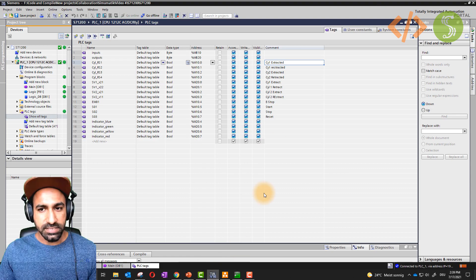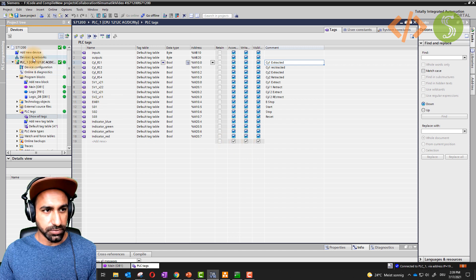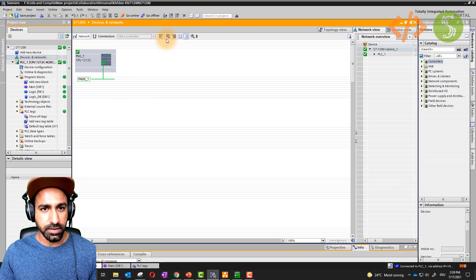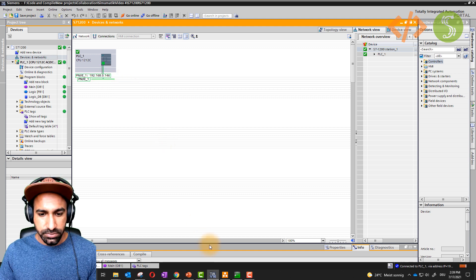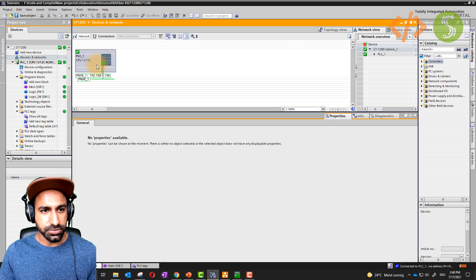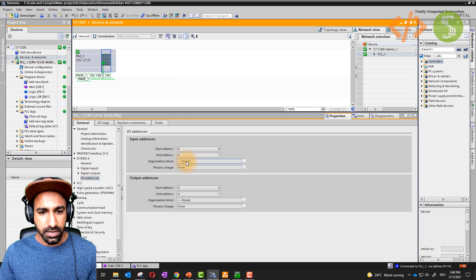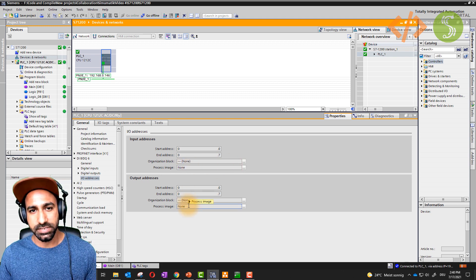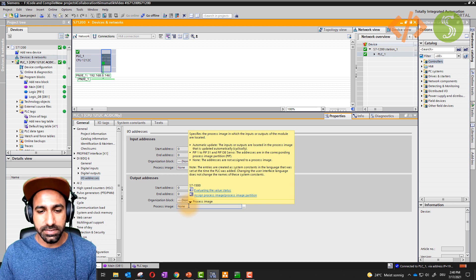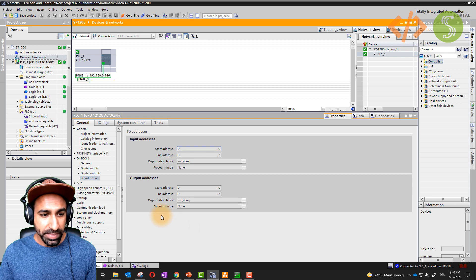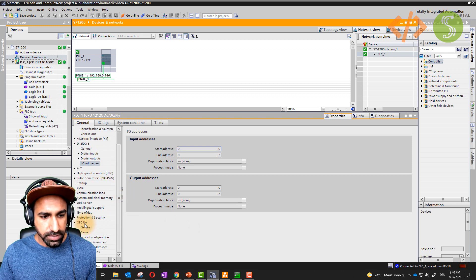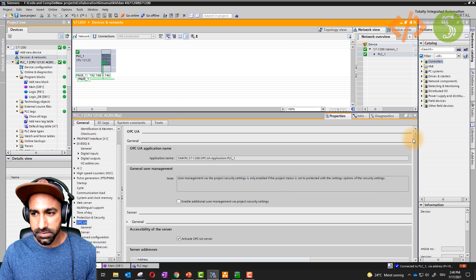Let's see step by step. First I'll open my TIA Portal, where I have defined my PLC. In Device and Network, my PLC is located here with IP address 192.168.0.146. Going to the properties of this PLC: first, go to the DI/DQ — the inputs and outputs — go to I/O address and remove the organization block, set everything to none, because we don't need to read inputs or give outputs directly; everything is done by OPC UA.